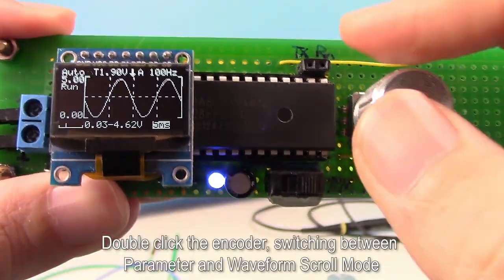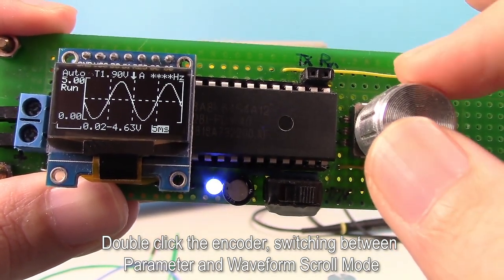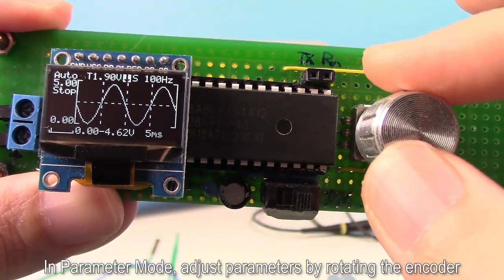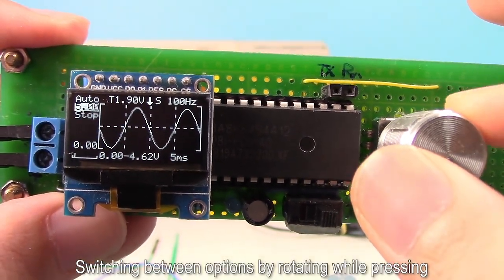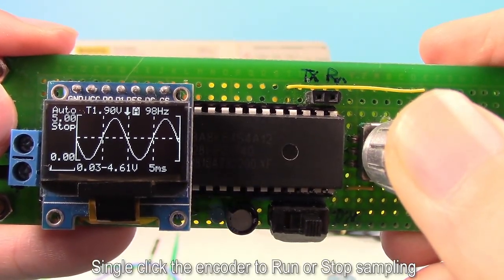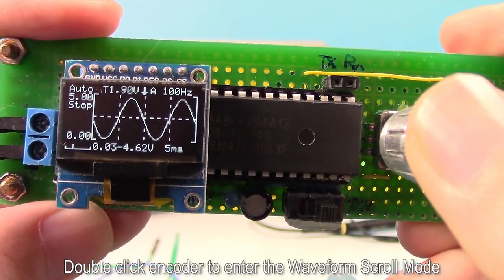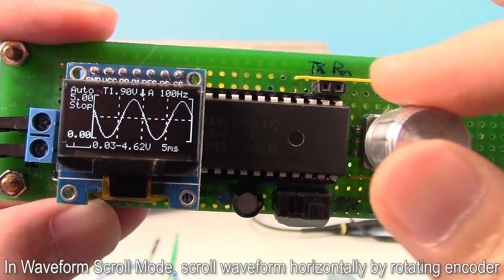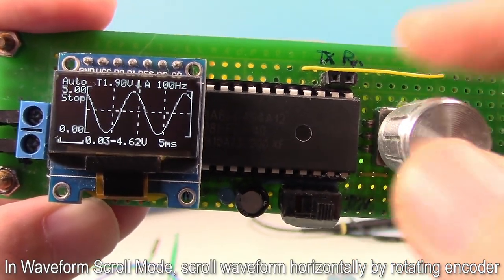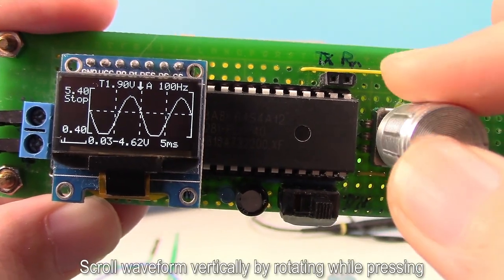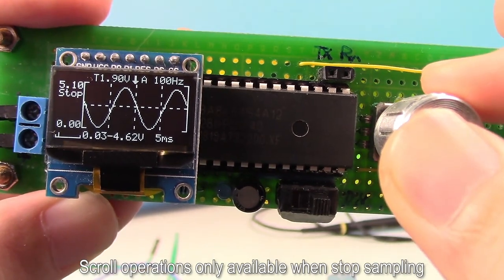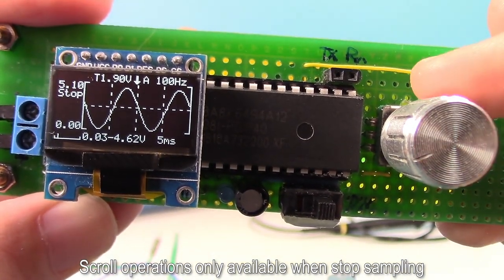Double click the encoder, switching between parameter and waveform scroll mode. In parameter mode, adjust the parameters by rotating the encoder. Switch between options by rotating while pressing. Single click the encoder to run stop sampling. Double click the encoder to enter the waveform scroll mode. In waveform scroll mode, scroll waveform horizontally by rotating encoder. Scroll waveform vertically by rotating while pressing. Scroll operations only available when stop sampling.